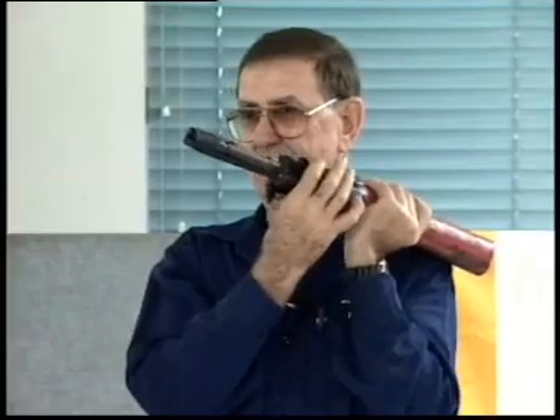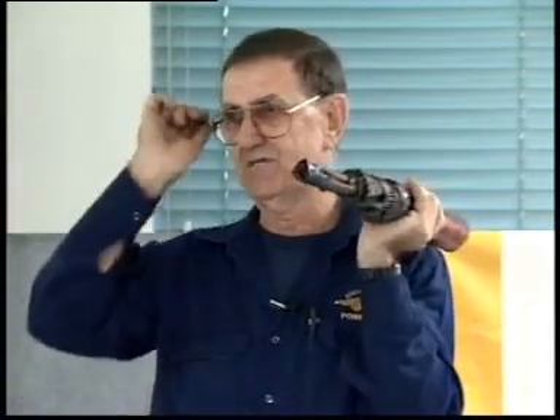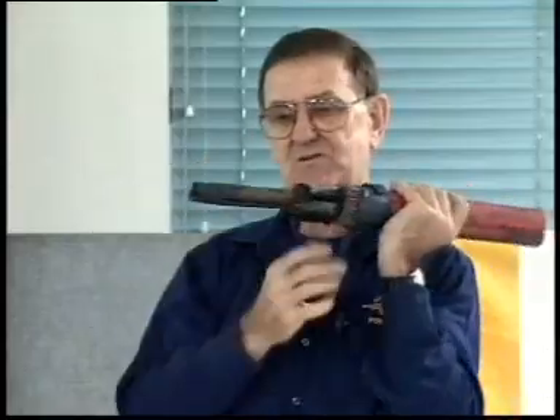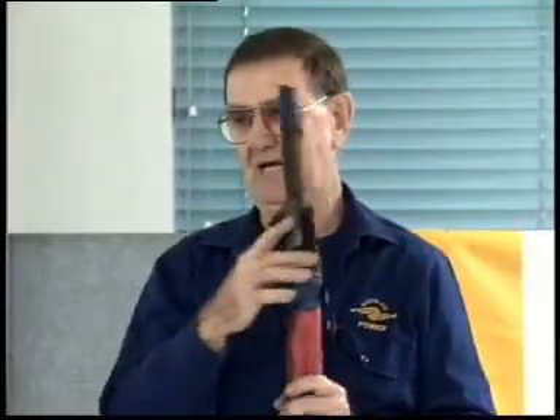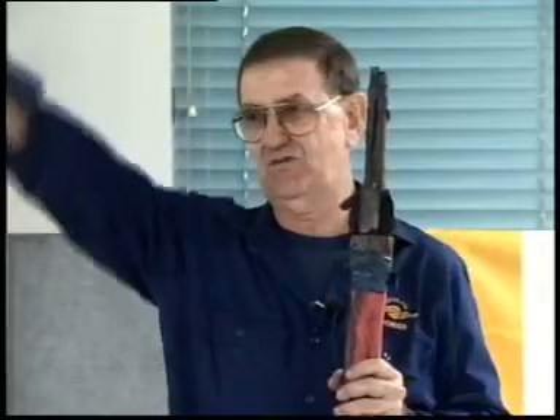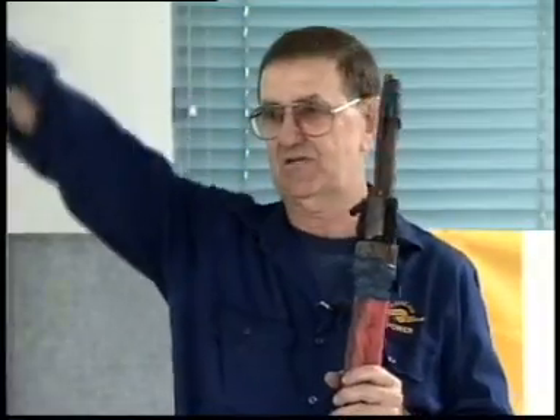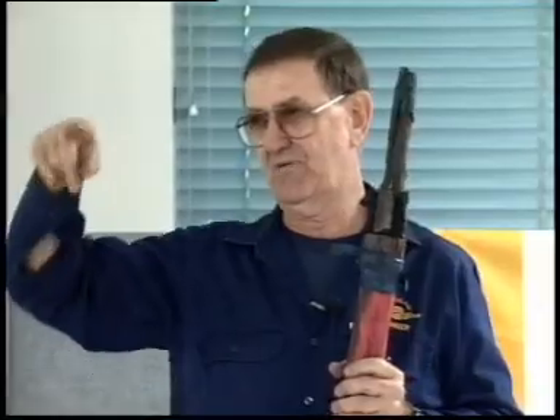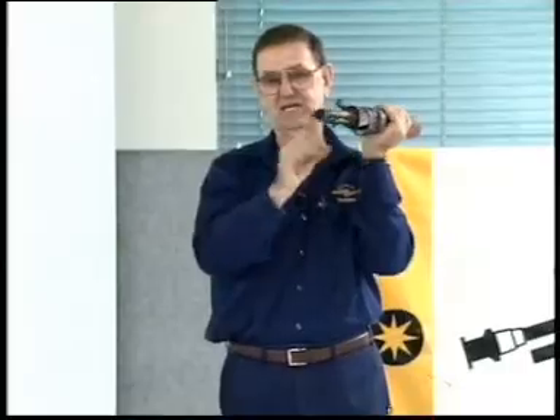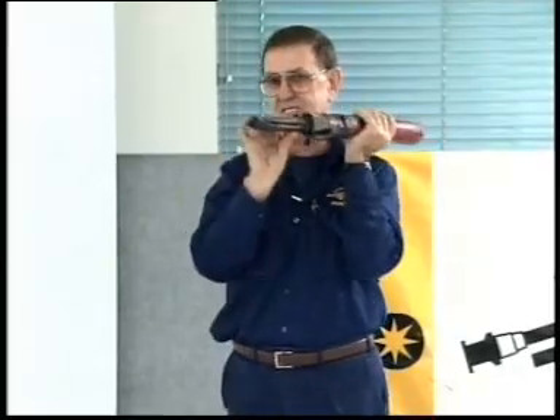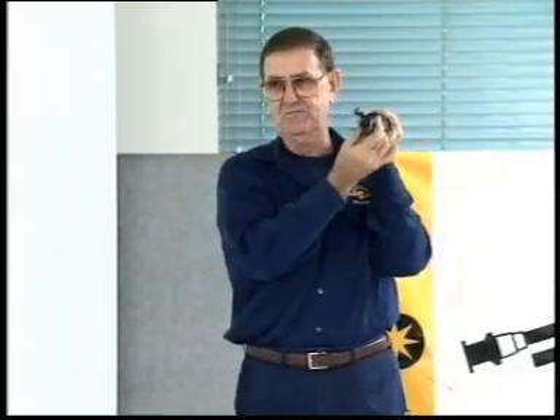Now the reason the lead cracks open is because it's bent too sharply, the cable's bent too sharply, or the plug's not handled correctly at the end. We normally find that the damage is done within the first metre, metre and a half at the back of the plug is where the damage is normally done, if it's not in the plug itself. And it's because the damage has been done to the cable from being bent too sharply. You bend this stuff too sharp, you're stretching the lead on the outside of the arc, and you're starting to make it ripple up on the inside. You're creating air voids. The thing that you don't need in this cable is to have any air voids between these phases, and that's exactly what occurs, and that's where we get problems, when we get air in there.